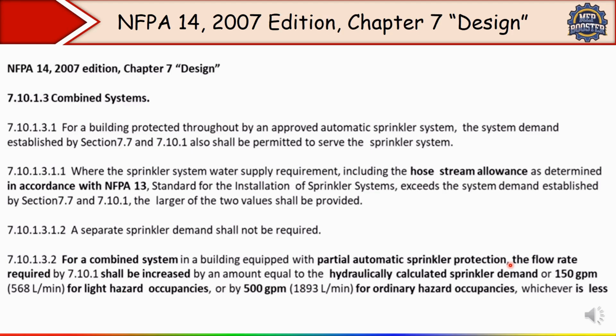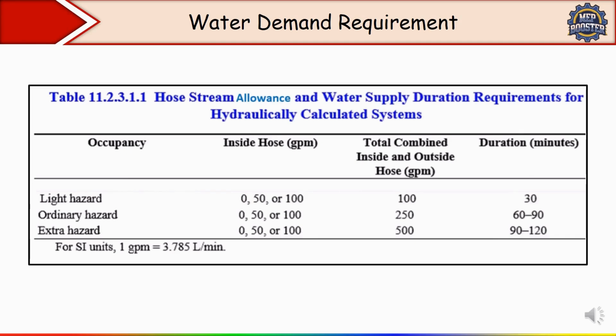Okay, clear? So here in this point it is described that for a combined system in a building equipped with, suppose in any floor you have installed the automatic sprinkler system, that is called partial. So with partial automatic sprinkler, for the water demand, the flow rate required by this table taken from the NFPA shall be increased by an amount equal to the outlined hose stream allowance demand and water supply duration requirement for light hazard, hydraulically calculated, or by 500 GPM. So let's see ordinary hazard occupancy and try to understand the table components.